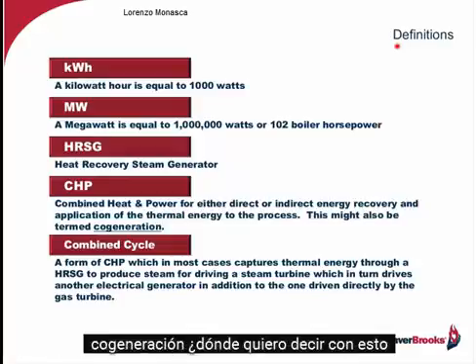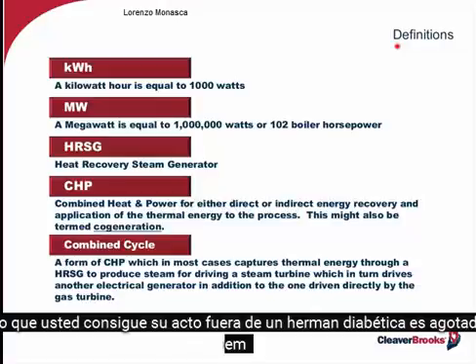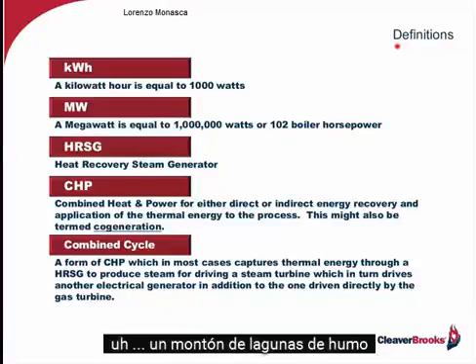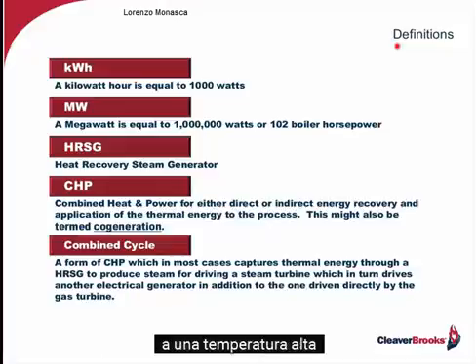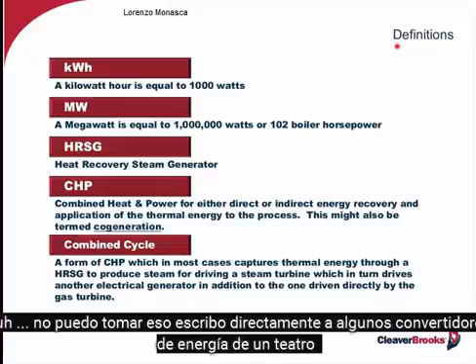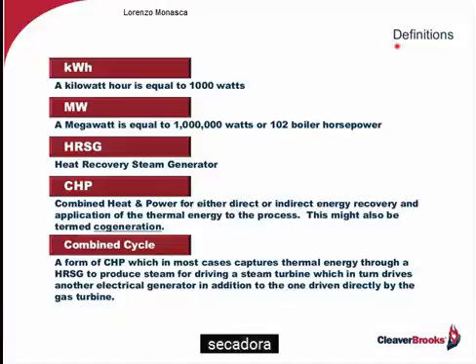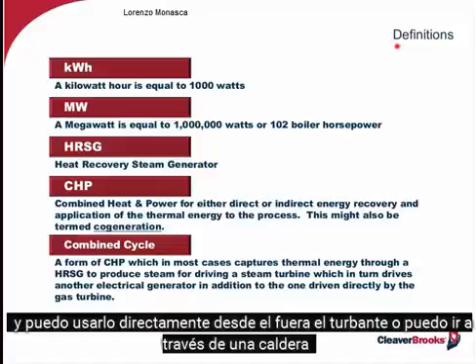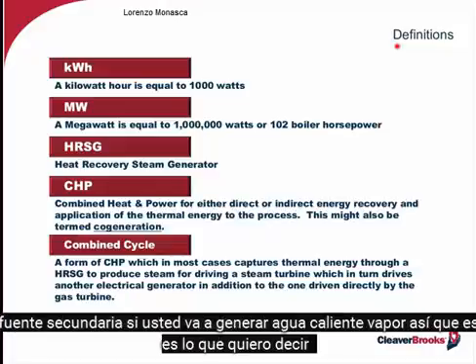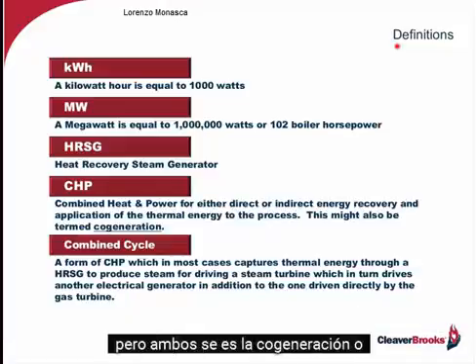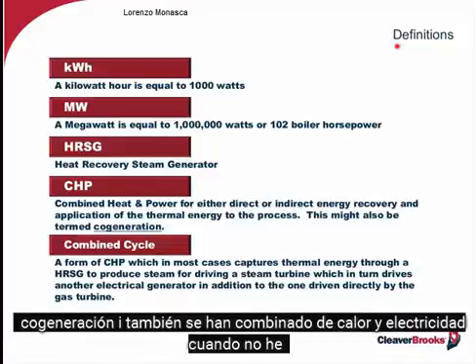What would I mean by that? Well, if it's direct, in other words, I've got a turbine. It's exhausting lots of gas at a high temperature. I can take that directly to some energy converters. Let's say it's a dryer, and I can use it directly off the turbine, or I can go through a boiler, a secondary source, if you will, to generate steam or hot water. So that's what I mean by that. But both of them, it's cogeneration or combined heat and power.